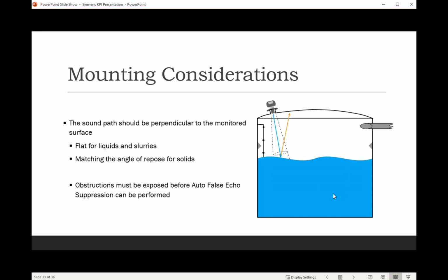Another thing to keep in mind is you can also use an ultrasonic transducer with a stilling well. We would recommend one long piece of pipe. We wouldn't want the bottom of the stilling well to become exposed either. And we want one long piece of pipe, because if there are seams in the stilling well, it could cause a false echo. Your reading could get stuck at that one seam. We could perform an auto false echo suppression with that, but it's easier to just have one long run of pipe for the stilling well.